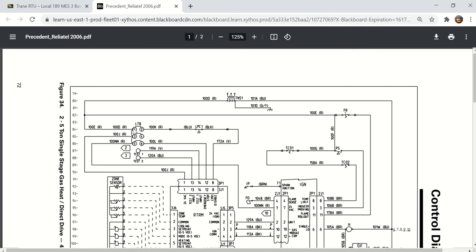It comes over to LTB1, low voltage terminal board 1. Then you see the jumper between 1 and 2, which is powering the low pressure switch, which goes to the compressor disable. So if you wanted to disable the compressor, you could remove that jumper between LTB 1 and 2. That would be the same as disconnecting the low pressure switch, or if the unit was completely out of gas, you would still disable the compressor. So here's the low voltage terminal strip, 1, 2, 3, 4, 5, 6. Here's where the 24 volt feeds into.